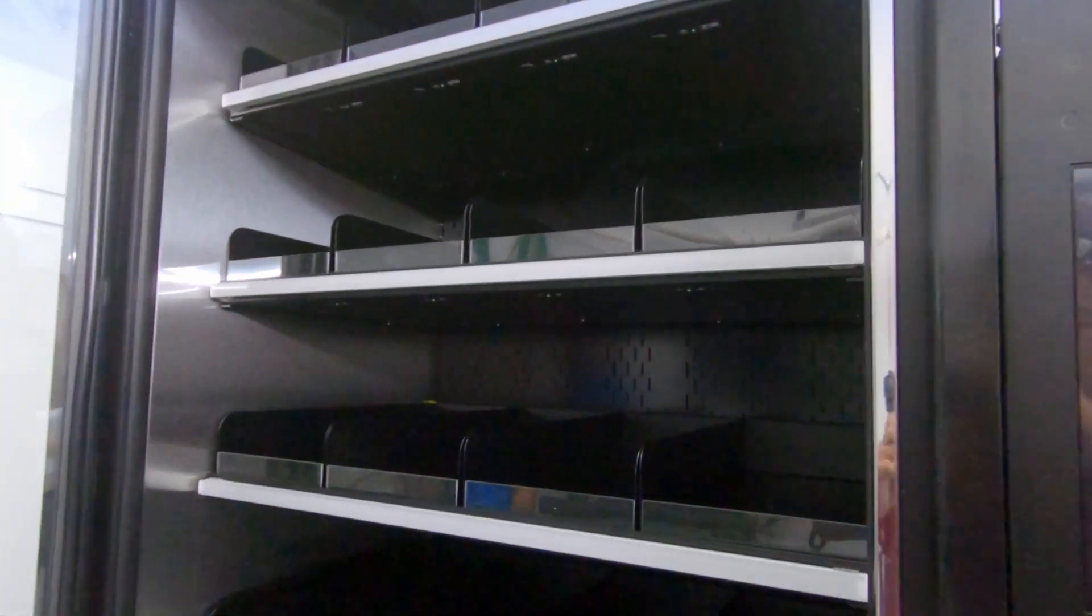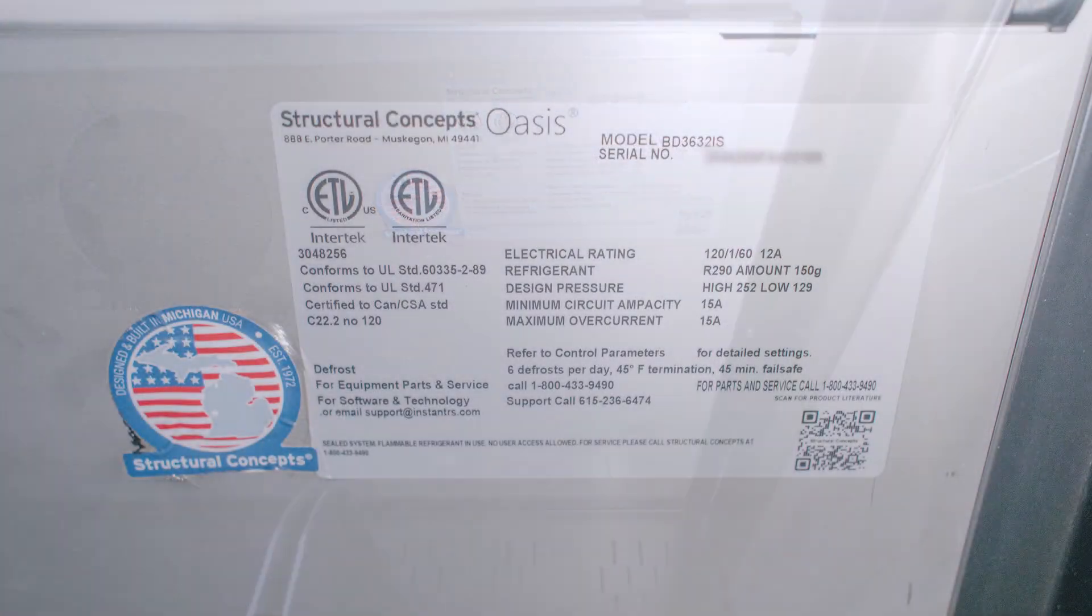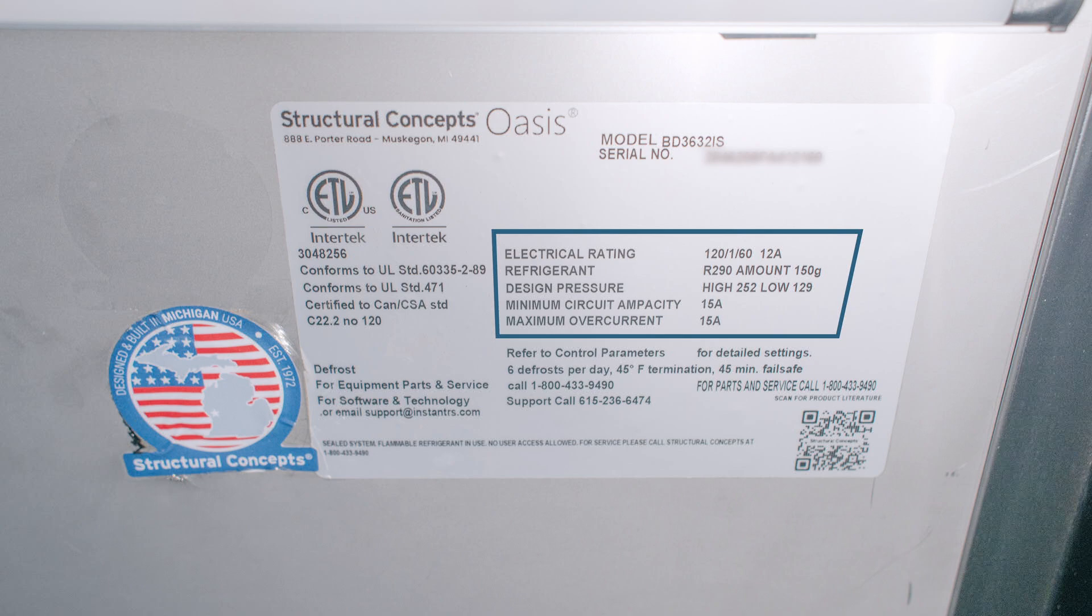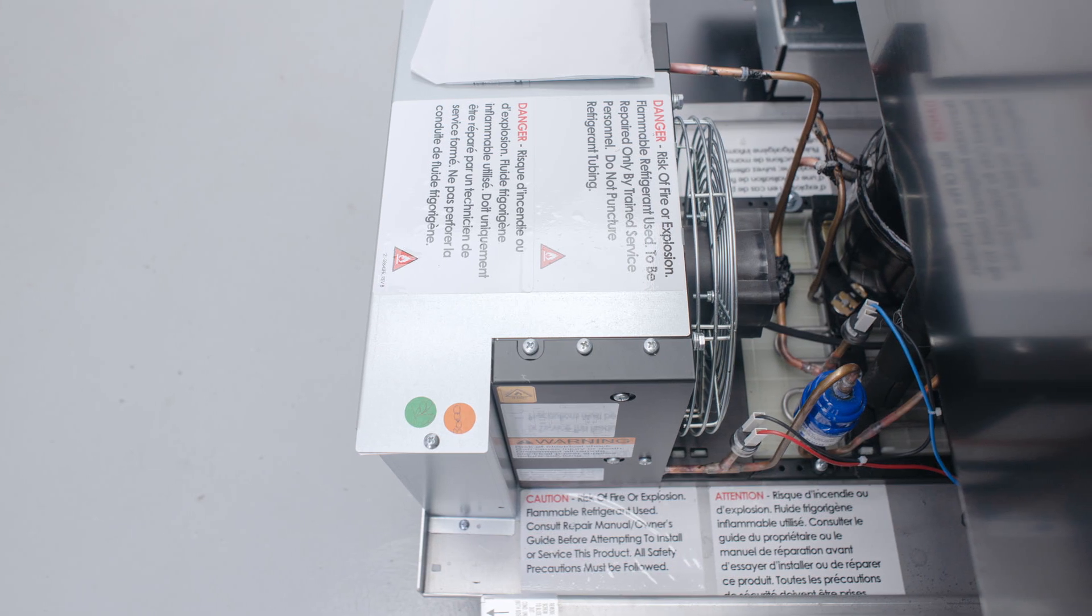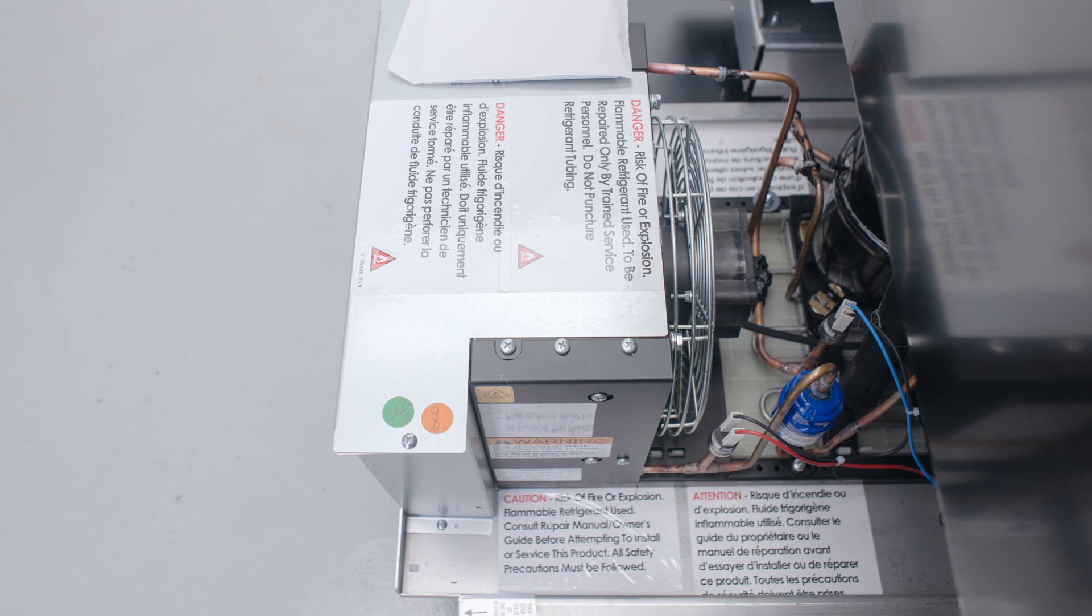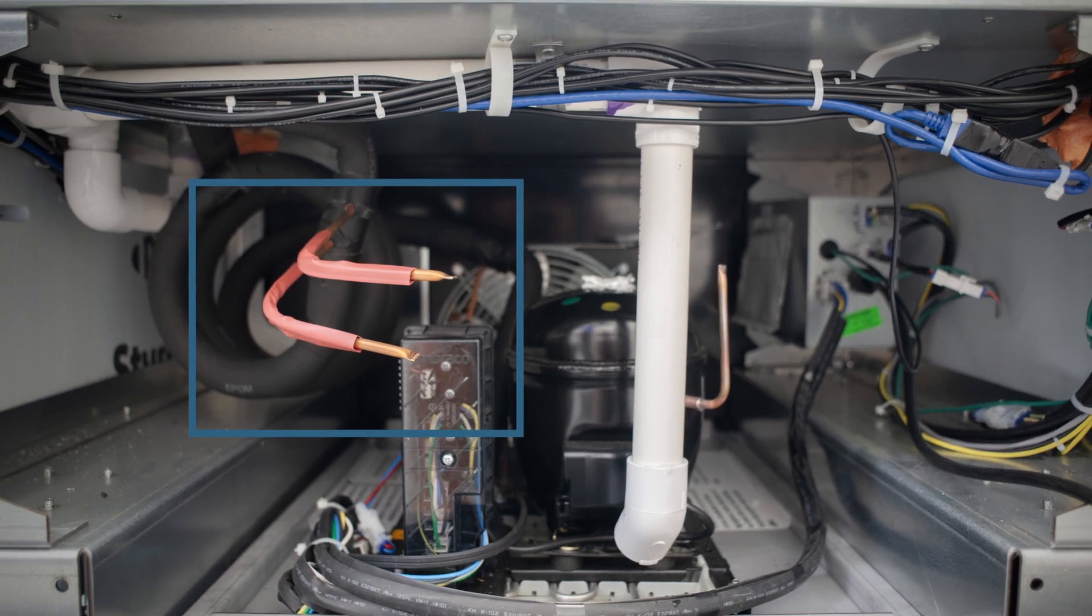To identify that the cabinet you're working on is using R290 refrigerant, check the serial label. We recommend taking a photo of the serial label for future reference. You will also see that the condensing unit is labeled as R290 and that the process ports are marked in red.